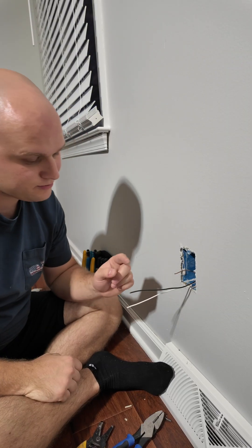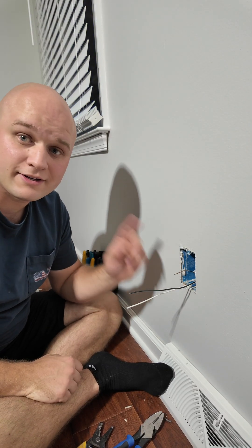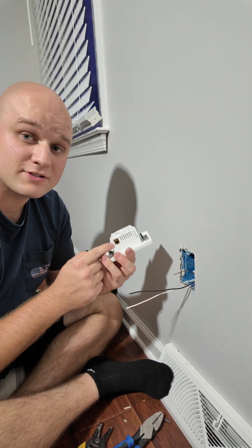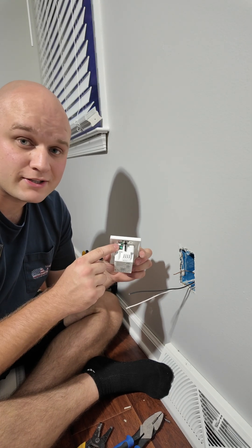The wires are all pigtailed now. We've got our hot, our neutral, and our ground. Now let's hook those wires to the outlet: the neutral goes to the silver lug, the hot to the brass lug, and the ground to the green lug.